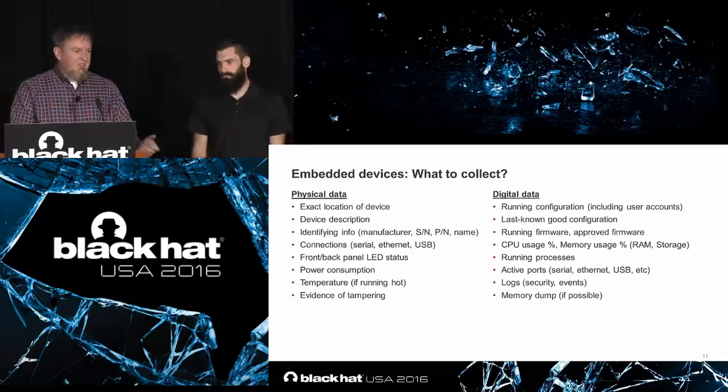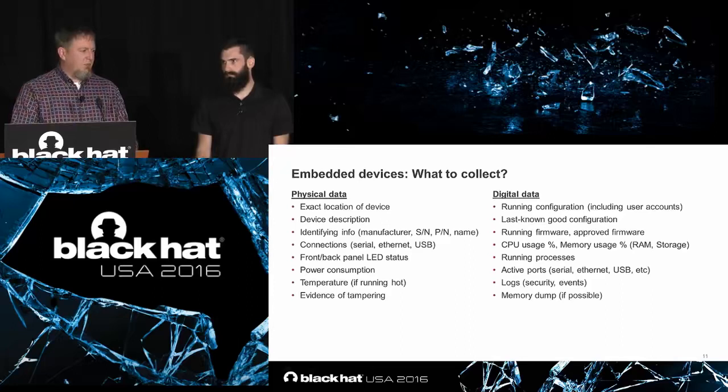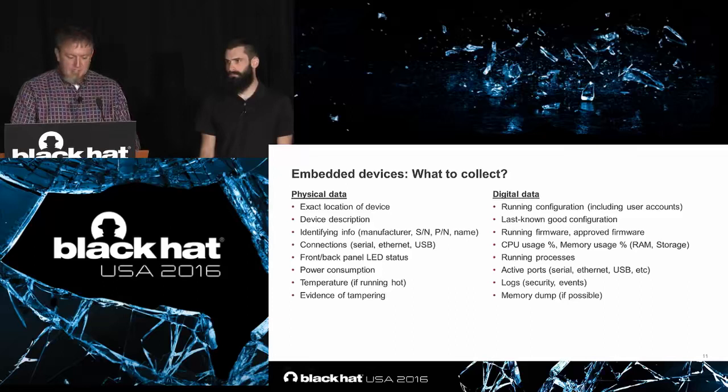What are the LEDs? Whenever I got a call and there was a problem in a substation, I'd send the technician out and say, well, what do the lights say on the front? Are they red and blinking, or are they all green and acting normal? See what the power consumption is.